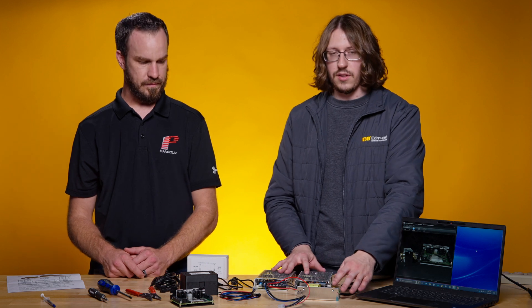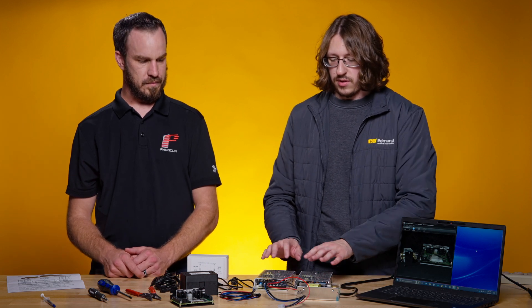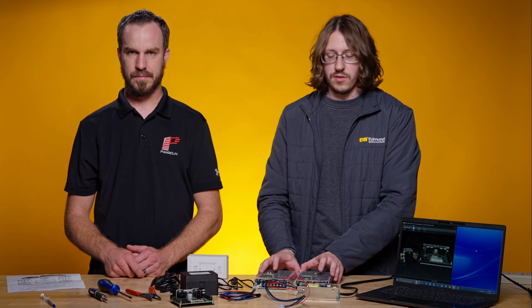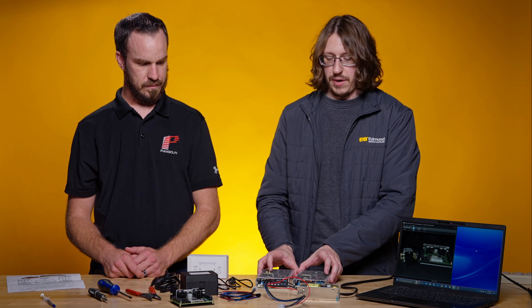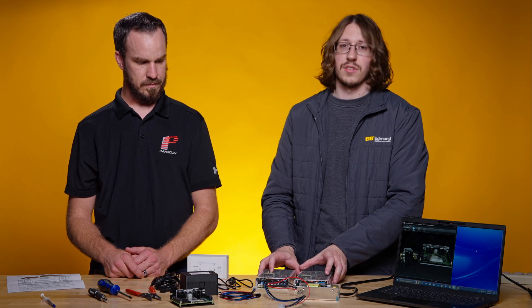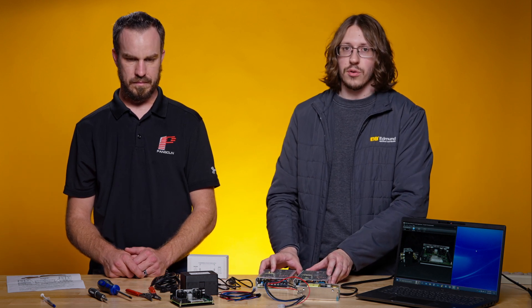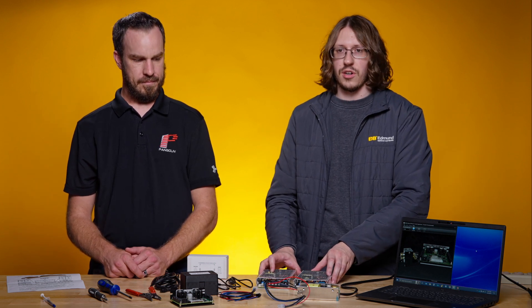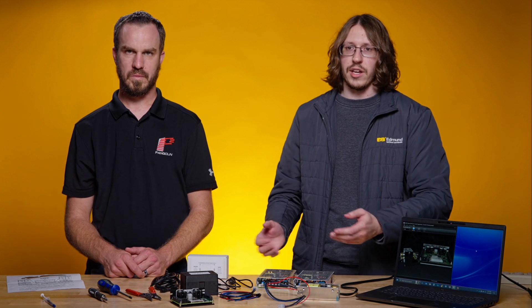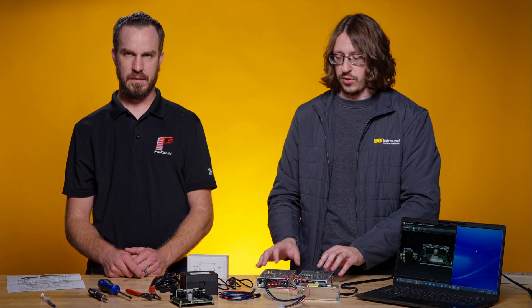Now for the European markets, due to EMC regulations and whatnot, we have to deliver two 24 volt power supplies. Again, please refer to the additional documentation that will be provided with your systems and also on the Edmund Optics website, but you're going to use your red plus 24 volt to one power supply. You're going to do your blue minus 24 volts to the minus on the other power supply. And then you're going to connect one black wire to the unused terminals on each power supply. And just to note, as Ryan said, these are sold separately. We sell these on our website. Customers can use their own 24 volt power supply as long as they ensure they have the right current and voltage.